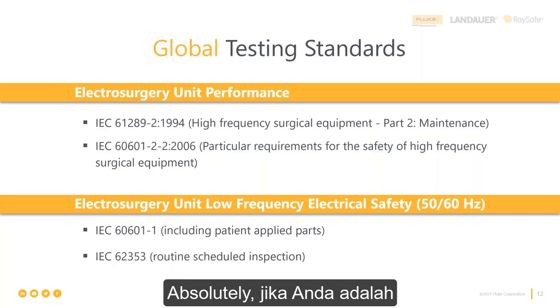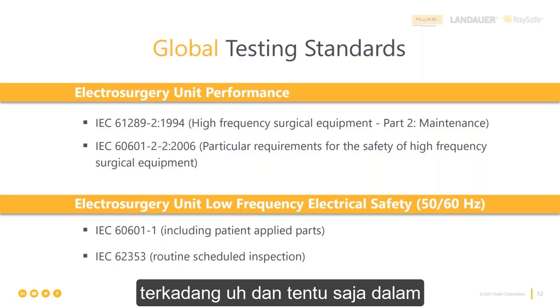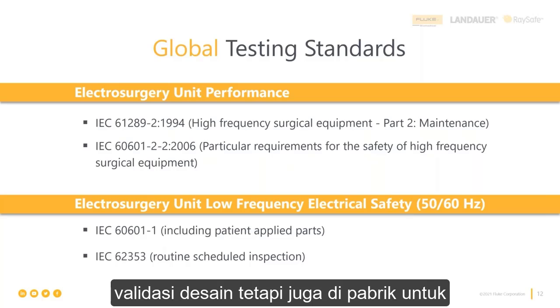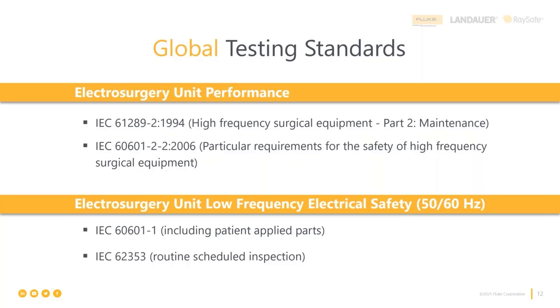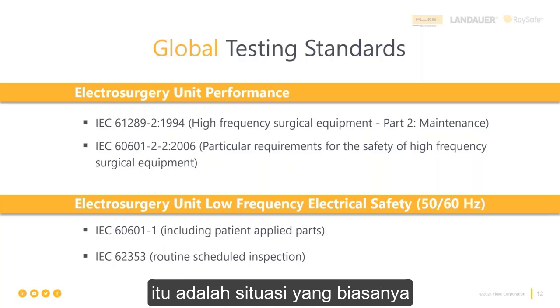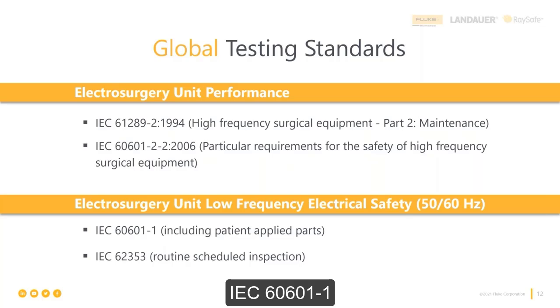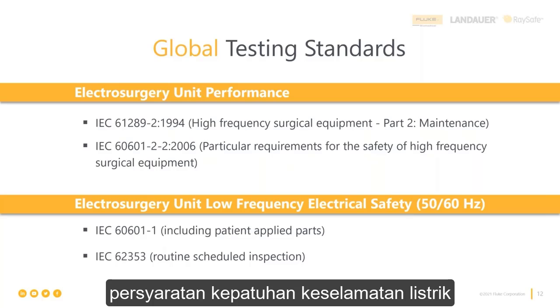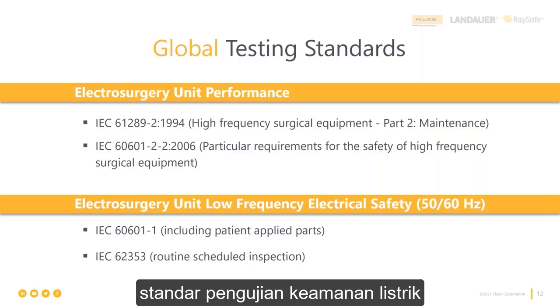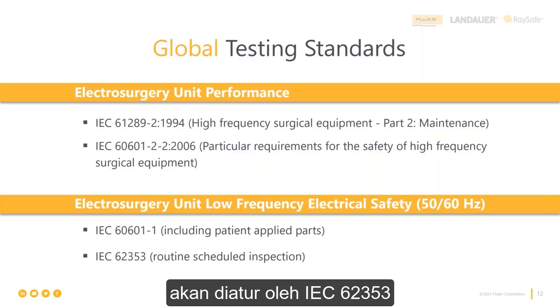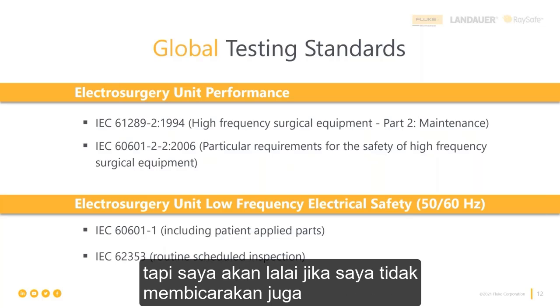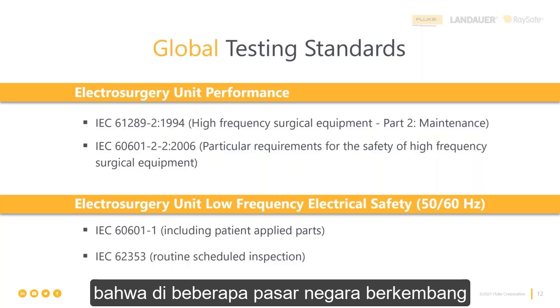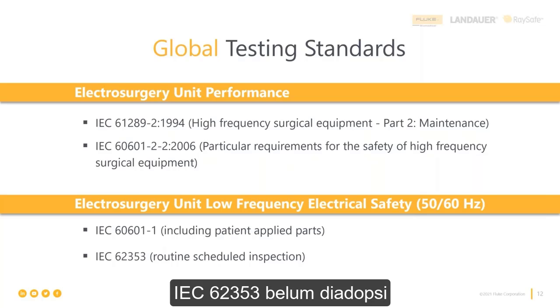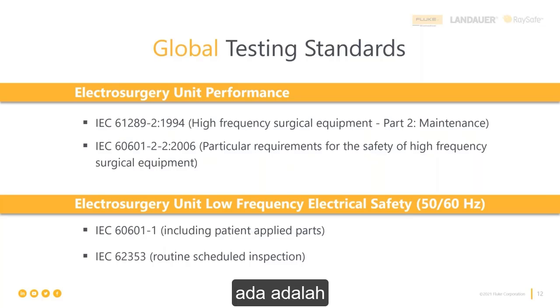So absolutely, if you are a medical device manufacturer, certainly in design validation, but also in the factory for final assembly testing, and sometimes in the repair depot, service depot, after the repair is done, those are situations that are typically IEC 60601-1 electrical safety compliant requirements. And all of the rest of the low frequency electrical safety testing would be governed by IEC 62353. But I would be remiss if I didn't also recognize that in some emerging market countries in the world, the IEC 62353 has not been adopted, and therefore the only international standard that there is is the IEC 60601-1.